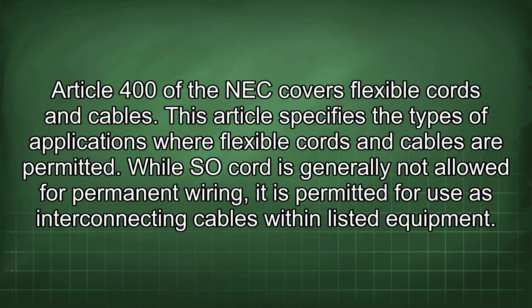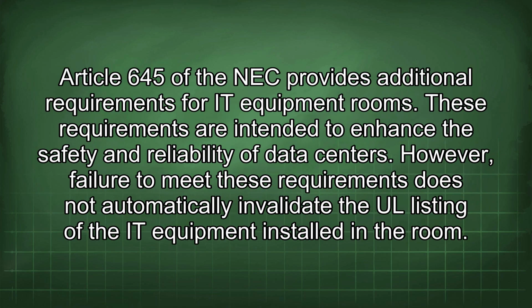Article 400 of the NEC covers flexible cords and cables. This article specifies the types of applications where flexible cords and cables are permitted. While SO cord is generally not allowed for permanent wiring, it is permitted for use as interconnecting cables within listed equipment. Article 645 of the NEC provides additional requirements for IT equipment rooms.